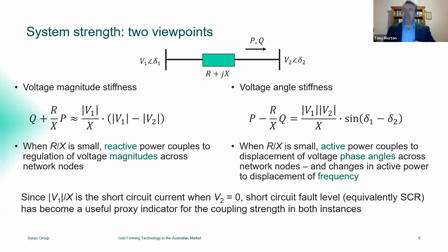If we've got a lossless network, then it is just Q. And that relates directly on the right-hand side to the difference in voltage magnitudes between the two endpoints, scaled by this quantity V1 on X. On the right-hand side, we've got another formula that talks about angle stiffness. And on the left-hand side of that formula, we have the active power flow P with a correction that again depends on the network resistance. And then on the right-hand side, that power flow P relates directly to the difference in phase angles between the endpoint voltages. And again, it's scaled by a V1 on X quantity. So both of these are determining at a very fundamental level and at a quantitative level how differences in magnitudes and angles of voltages relate directly to differences in the active and reactive power flows.